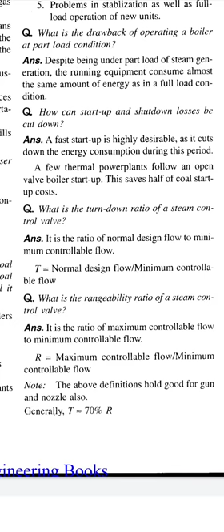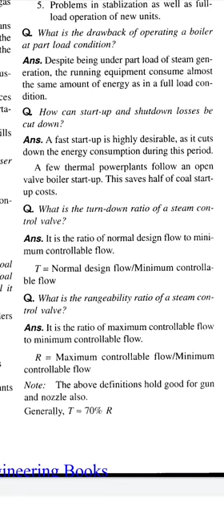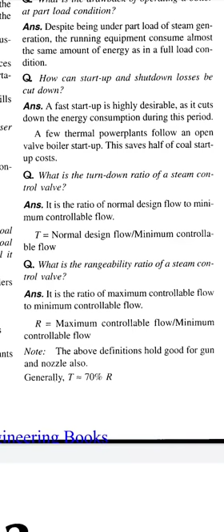Question: what is the turn down ratio of a steam control valve? It is the ratio of normal design flow to minimum controllable flow. Turn down ratio equals normal design flow divided by minimum controllable flow. Question: what is the rangeability ratio of a steam control valve? This is the ratio of maximum controllable flow to minimum controllable flow. Rangeability ratio equals maximum controllable flow divided by minimum controllable flow. The above definitions hold good for gun and nozzle also. Generally T equals 70% of R.